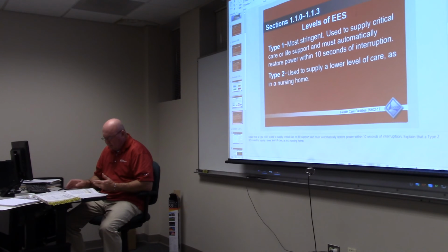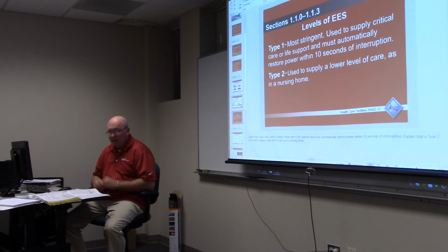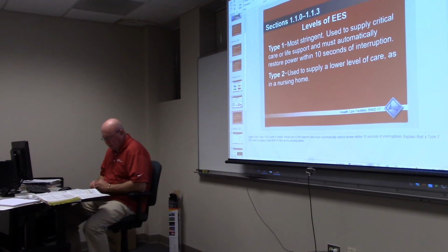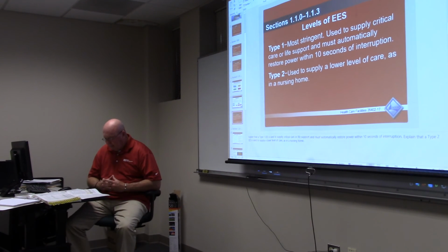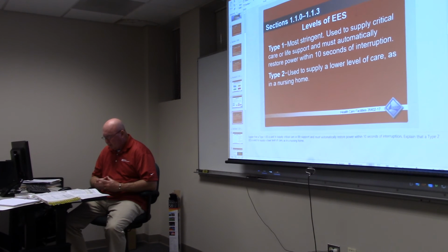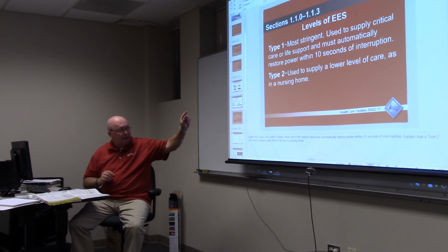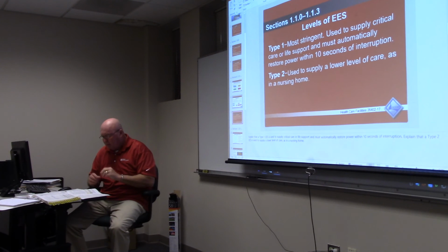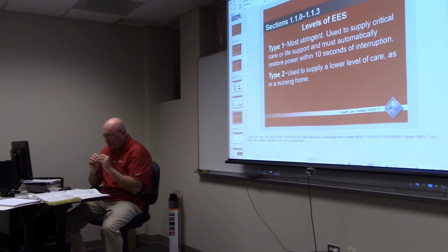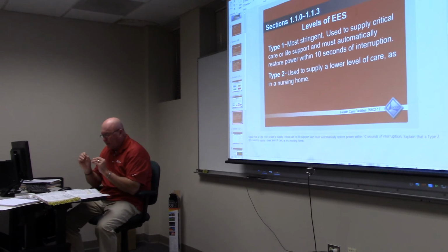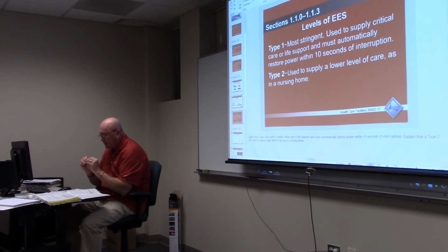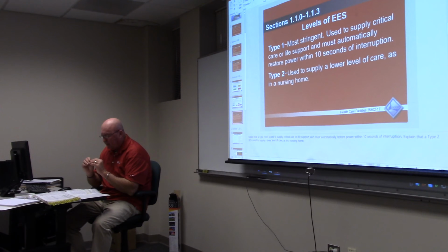Therefore, the branches of the emergency system are actually similar to type 1 because they are overnight, they could be on something critical and it needs backup power possibly. So if we read down through here, even though it's type 2, it's a little less stringent, a lower level of care as in a nursing home, but yet it's still important, isn't it? If there are some essential electrical systems inside of this facility. On page 5, the top paragraph says essential electrical systems for limited care facilities and nursing homes must have 2 separate branch circuits, just like the other.